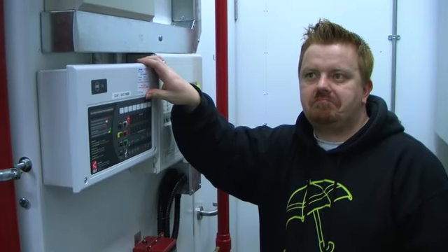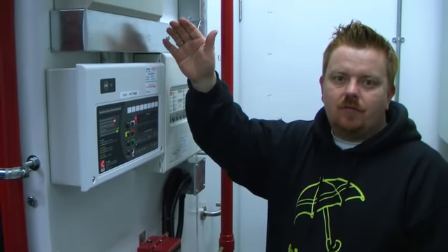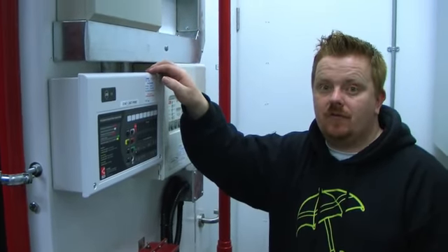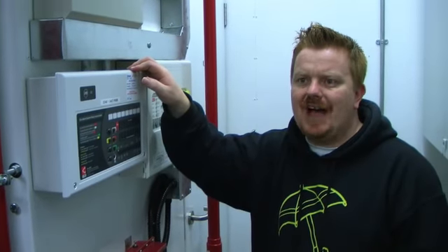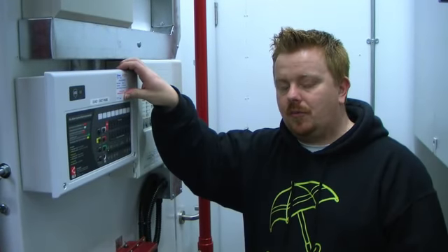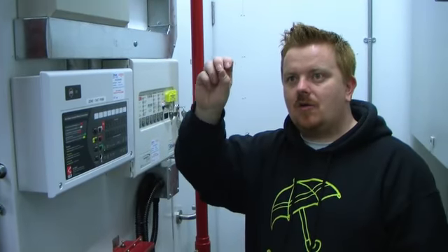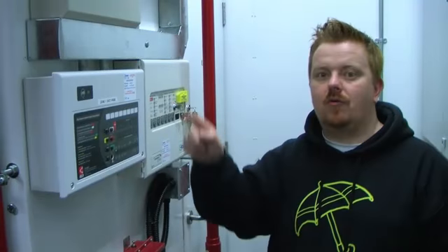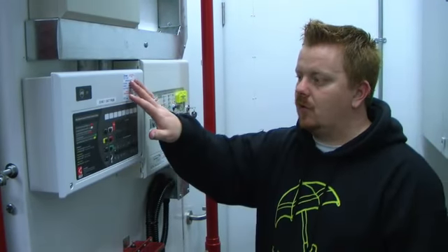So in the cold air supply from outside, we're sampling the air for contaminants. Let's call them smoke particles for one, or other contaminants such as large volumes of sand, or let's say you're in the desert for example and you had a sandstorm coming your way. The duct probe would detect the increase in particles in the air and switch the chillers on and go full recirc. So that's what the duct probe does.